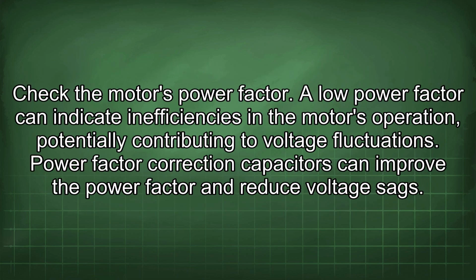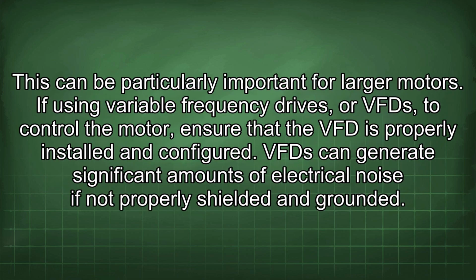Check the motor's power factor. A low power factor can indicate inefficiencies in the motor's operation, potentially contributing to voltage fluctuations. Power factor correction capacitors can improve the power factor and reduce voltage sags. This can be particularly important for larger motors.